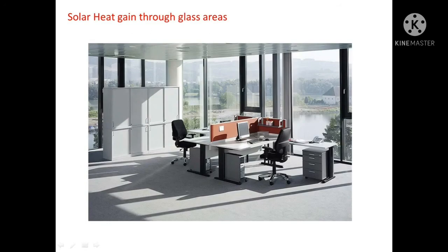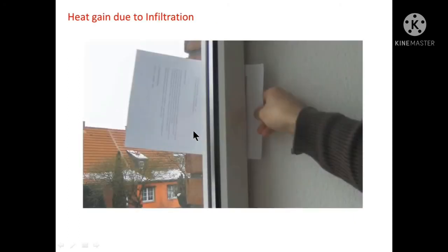Next is solar heat gain through glass areas. Through glass, solar heat gain can also occur; generally the value of solar heat gain through glass areas is given in the problem. Next is heat gain due to infiltration — there are various gaps in windows and doors, and heat gain from these gaps can be calculated by the product of mass flow rate and the enthalpy difference between outside air and the air of the conditioned space: Q = m·Δh.